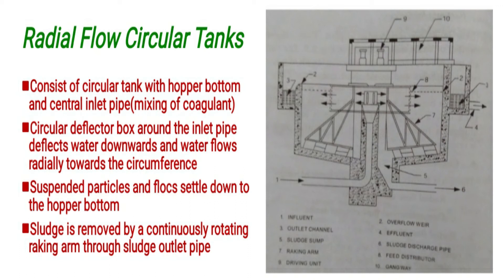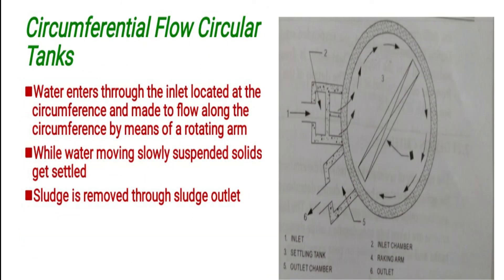Suspended particles and flocs settle down to the hopper bottom. A raking arm continuously rotates, and through the raking arm, the sludge is removed via a sludge outlet pipe. The second type of circular tank is the circumferential flow circular tank.